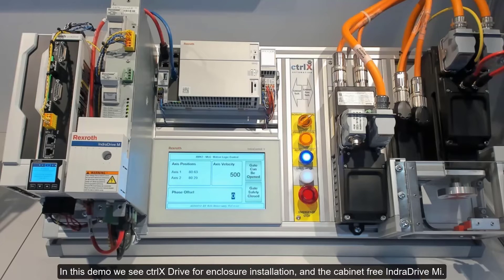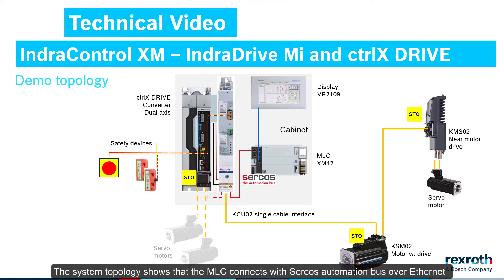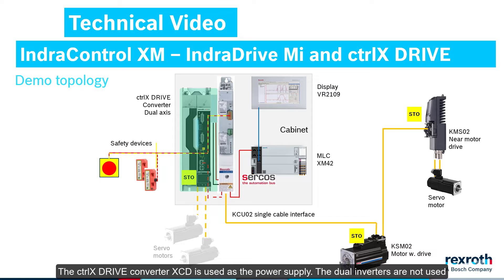In this demo we see ctrlX Drive for enclosure installation, and the cabinet-free IndraDrive Mi. The system topology shows that the MLC connects with Sercos automation bus over Ethernet, with the hybrid cable to the cabinet-free motor drive KSM-02 and near motor drive KMS-02. The ctrlX Drive converter XCD is used as the power supply. The dual inverters are not used, and no motors are connected, because of the demonstrator space constraints.